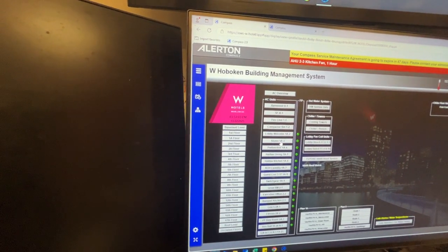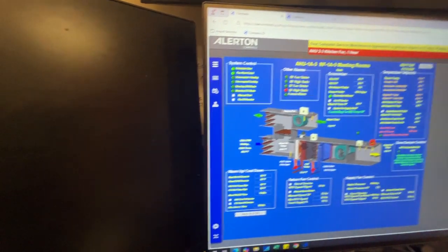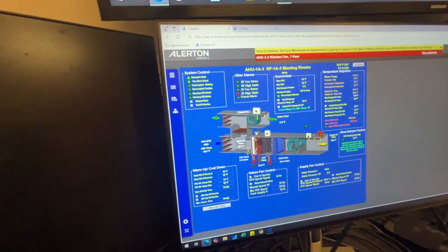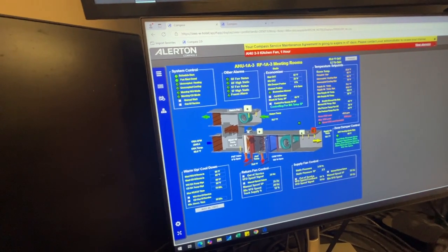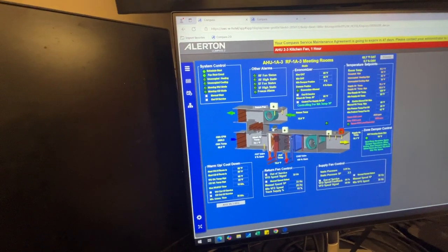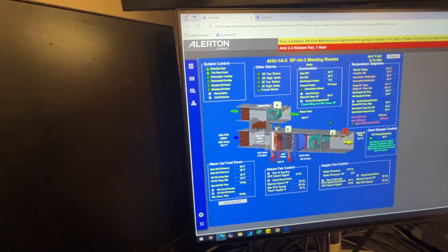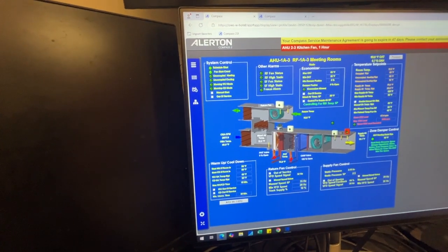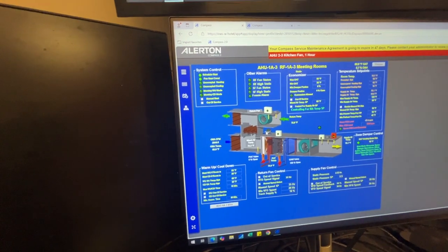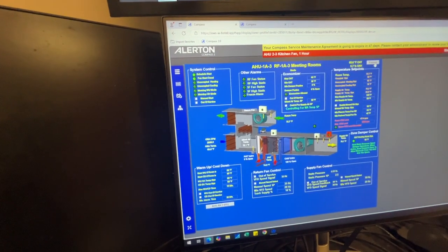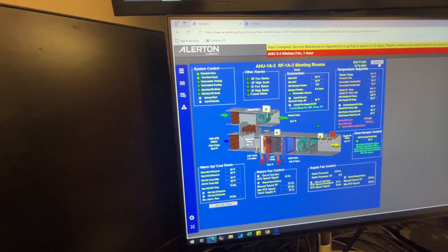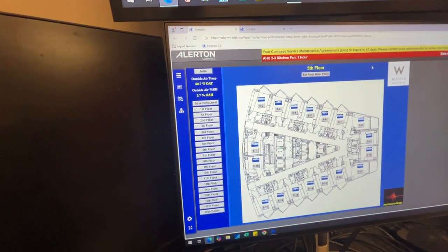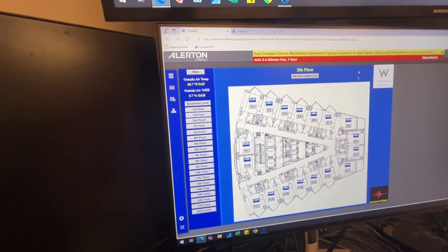There is a project that I'm giving to Joanna on the studios. This outside air damper for 1A2, 1A3, and 1A4 is completely closed on the roof. It has been since opening. They installed the outside air damper upside down. So they're closed, permanently closed. There's no outside air coming into the pre-function, the studios, and the lobby. Hopefully that will be fixed in the next 2 months.